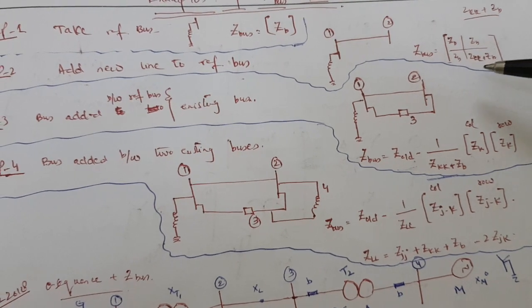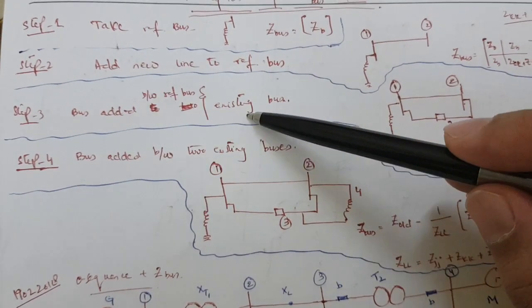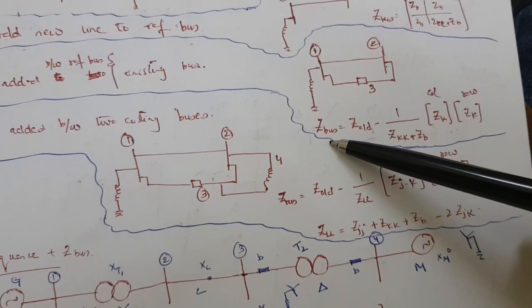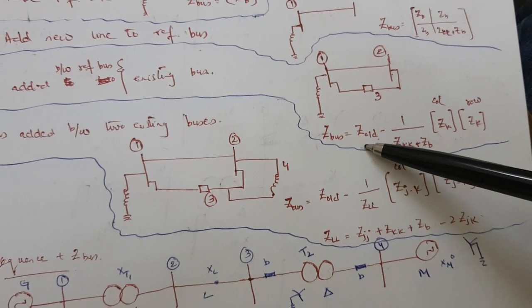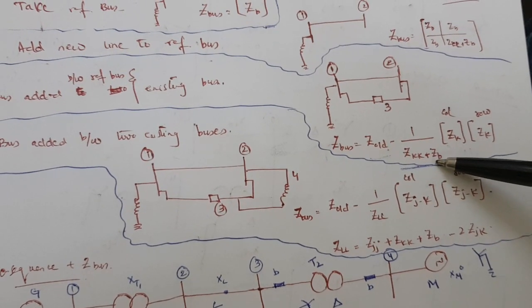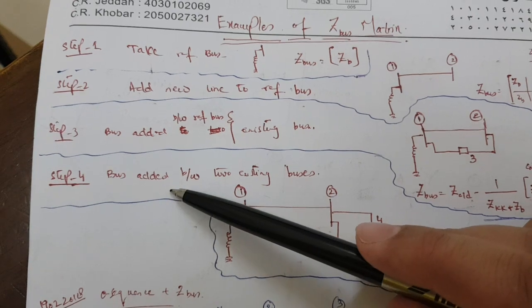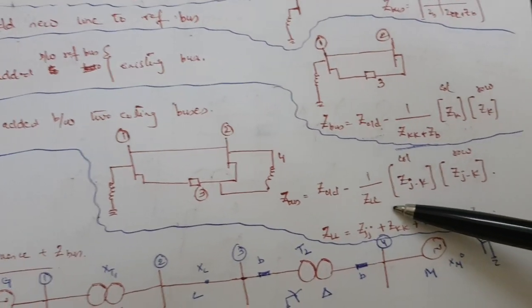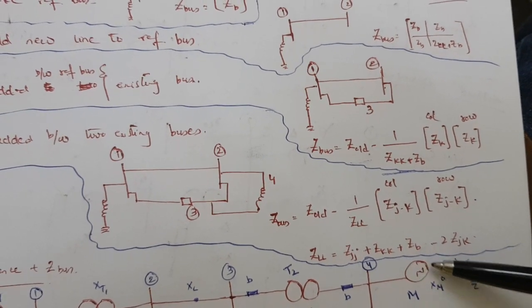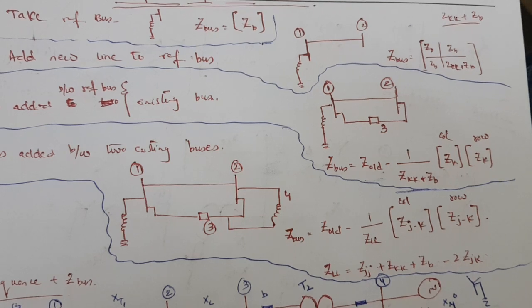Step three: if we have to add a bus between the reference bus and an existing bus — where the reference bus is the one connected with ground — we use: Z-bus new equals Z-matrix old, with one over Z-kk (the line to be added) plus Z-b (the reactance of the line), and the Z-k column and Z-k row. Step four: if the bus is added between two existing buses, we use the formula with one over Z-ll, where Z-ll equals Z-jj plus Z-kk plus Z-b minus 2·Z-jk.